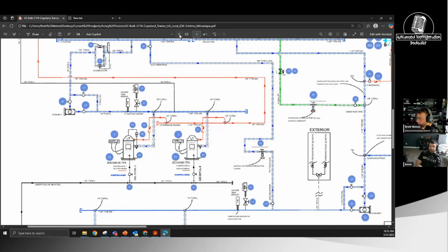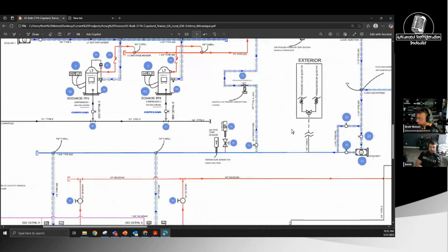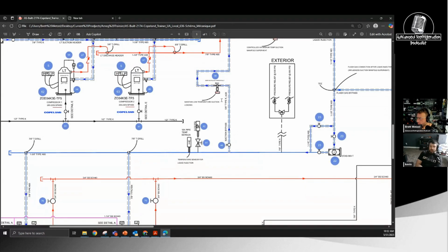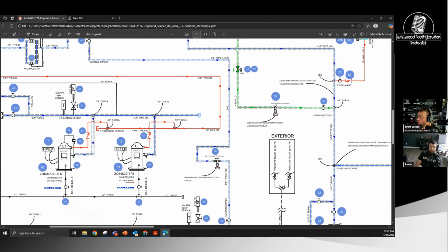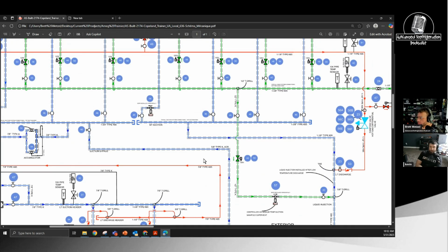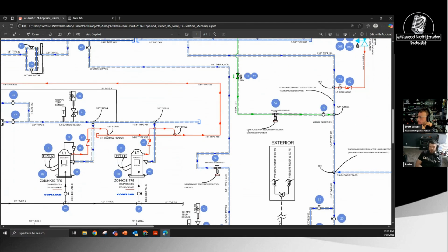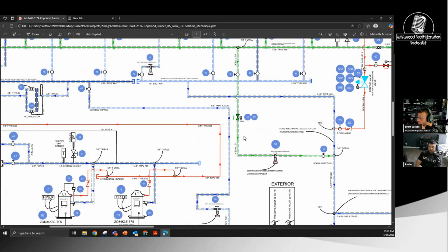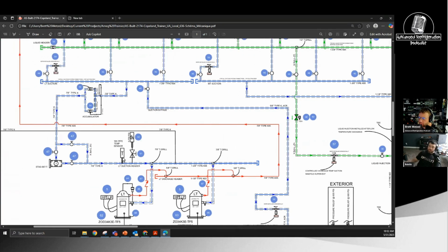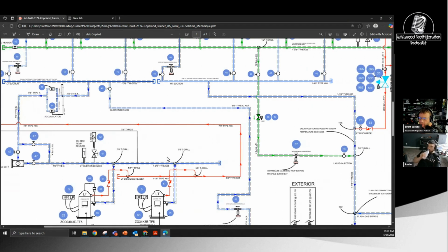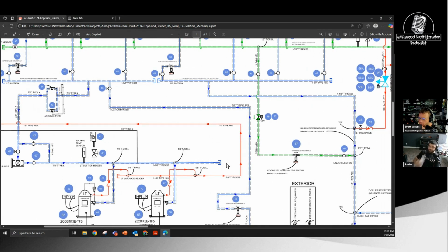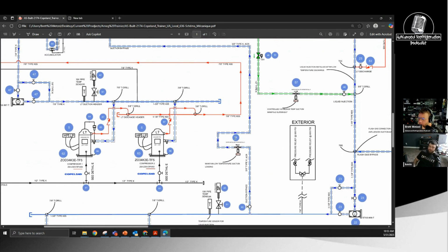What is this suction bypass thing? So that was there for, I believe, the medium temp to low temp. Oh, load shedding. Okay. All right. Sorry. We really didn't have to mess with it much. It was there just to keep any issues from happening. But I guess it's a trainer, right? So if you only have, let's just say, 2 or 3 loads, and one goes into a defrost, the unloader can only unload so much, right? Yeah. So essentially, it just takes some of the medium temp and throws it in there via the M12 here.